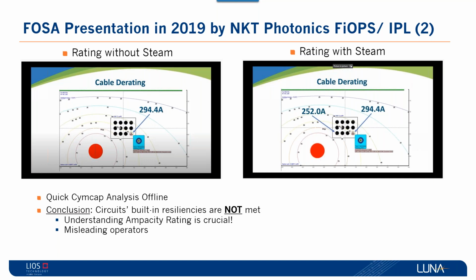One thing they mentioned in that presentation, at the end on the left, is something called rating, and how you can derate a circuit simply because there's a steam line. In that FOSA webinar, the first thing explained was that the contingency plan, part of the resiliency built in, was to be able to push 294 amps in those medium voltage distribution circuits. However, the steam line is affecting the entire duct bank, and what they show here is the ability to do an ampacity calculation and understand the rating of the cable if it is next to the steam line.